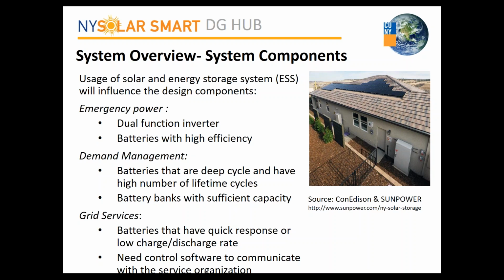And so in this situation, you would need batteries that have a high number of life cycles and deep cycle consideration. The battery bank has to be large enough to cover your demand so that you can actually provide power during the time of your peak demand and shift that. If you want to use the batteries for grid services, where you provide ancillary services like frequency and voltage regulation, then you should use batteries capable of quick response. You'd have software that communicates with your utility so they can use your batteries for frequency and voltage regulation.